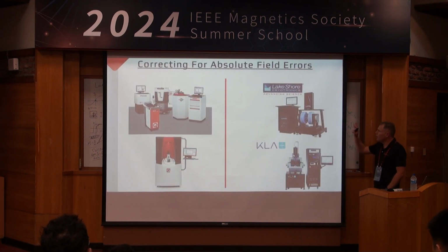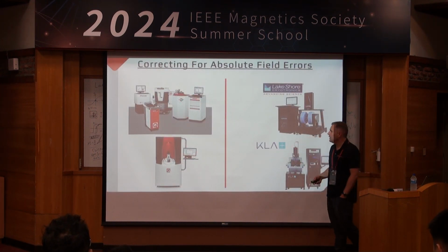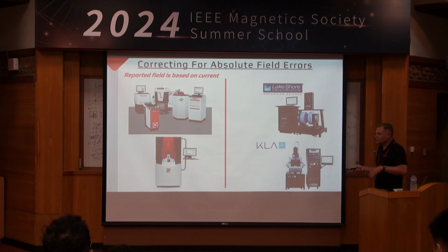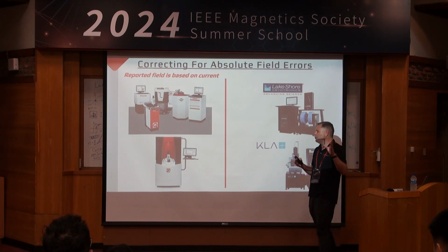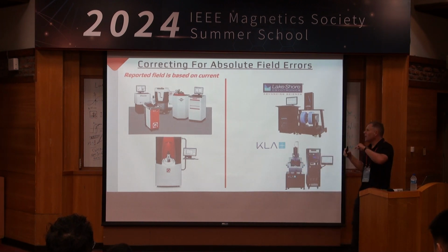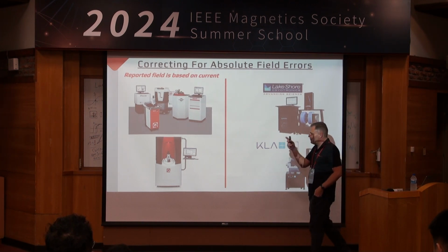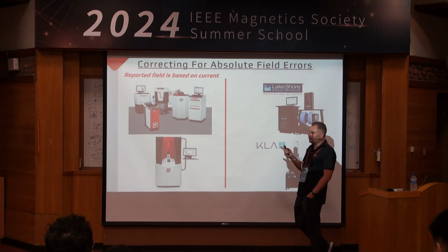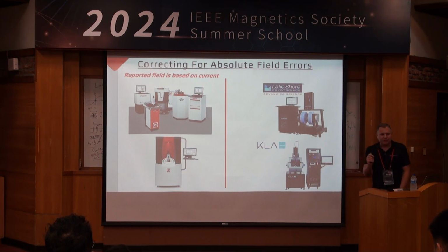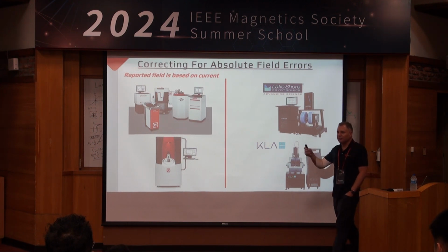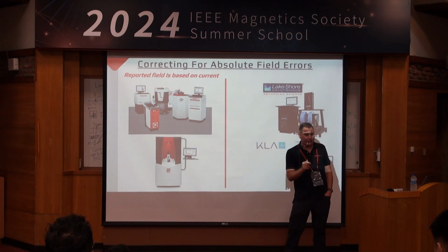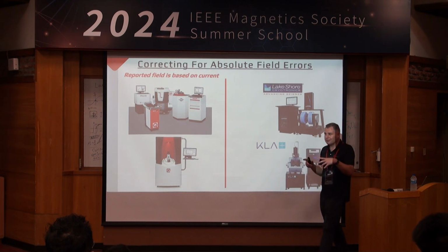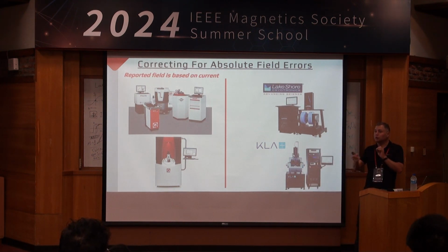So again, let's go back to our more traditional VSMs and the Quantum Design systems. The first thing I learned, this is back when I was an undergrad at UC Davis, and I was using the old MPMS. What the lab manager said to me was, hey, that field that is reported in our software, MultiVu, many of you are familiar with MultiVu, that is not based on a sensor like, let's say, a Hall sensor or a Gauss sensor. All that's based on is the current to the magnet. But we're dealing with superconducting magnets, and superconducting magnets are very good at holding on to flux or trapped currents. And therefore, when the system says it's at zero field, it might not be at zero field.